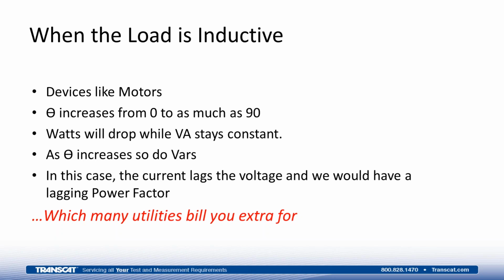In many areas of the country, utilities bill you for the power factor as an increased charge. The rationale behind it is the fact that if you didn't bill for the power factor, people who had more motor loads would be paying less in energy than people who had a purely resistive load. So they have VAR compensating meters that are used in the industry, specifically in the industrial sector, as you apply those motor loads, to properly bill you. They have a power factor penalty, which they would charge you. They wouldn't look at the power factor of an individual load. They would look at the power factor of your facility, and as a result, bill you for the use of energy in an inductive fashion, which costs them more to produce than in fact you're using.